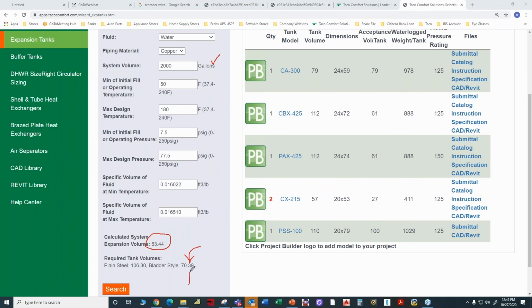So now I no longer need a steel container that's a minimum of 95 gallons. I only need a steel container of 70 gallons. The expansion or acceptance volume is still the same, but the tank physical volume is smaller. So whenever you move the expansion tank from the lowest part of the building to the highest part of the building, the expansion tank always gets smaller. That's one of the consequences of moving the tank, changing its elevation. Okay, and one other thing I wanted to point out. Let's erase all this stuff.